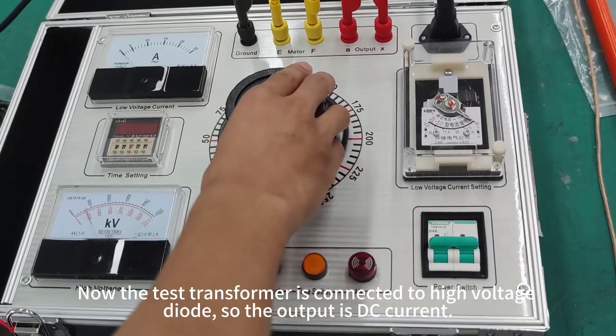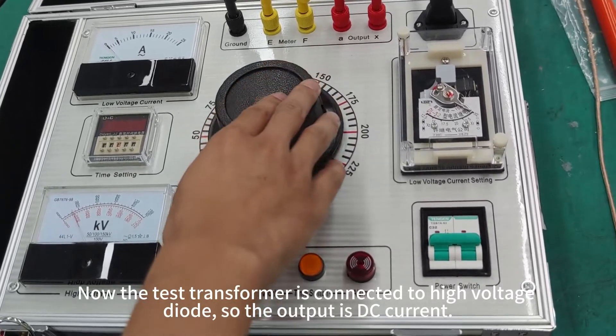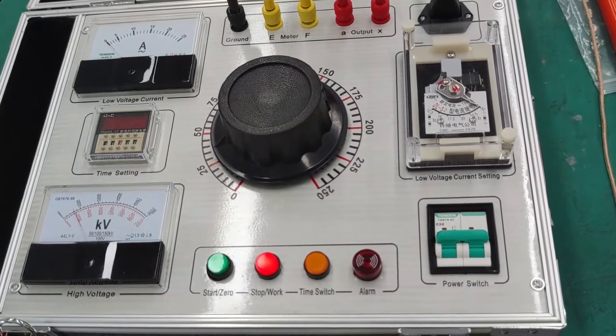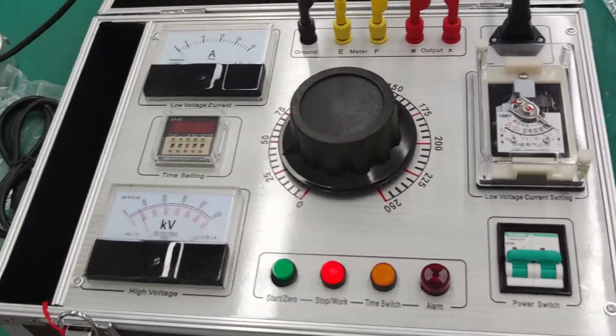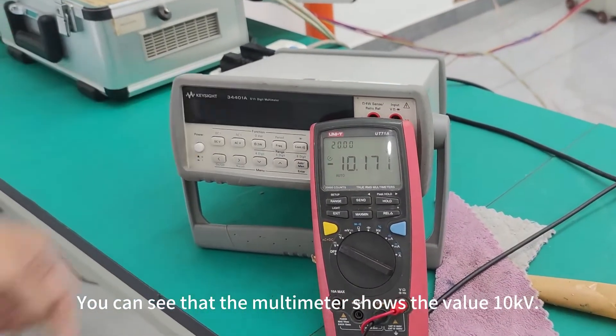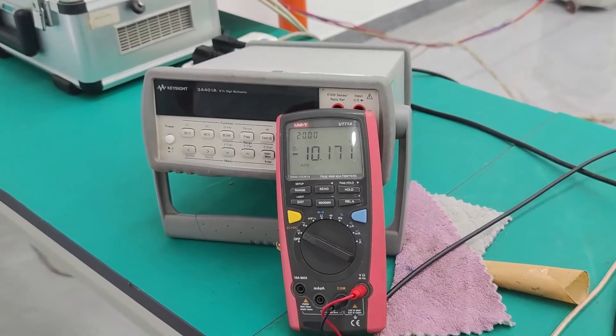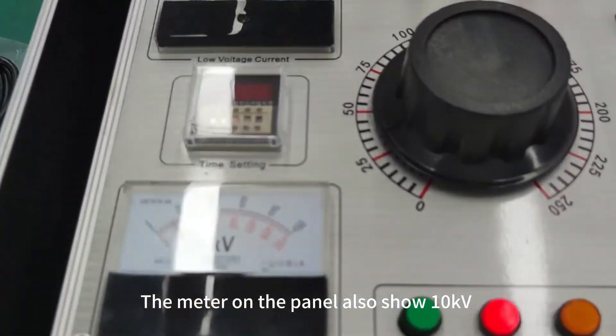Now the test transformer is connected to high voltage diode, so the output is DC current. You can see that the multimeter shows the value 10K. The meter on the panel also shows 10K.